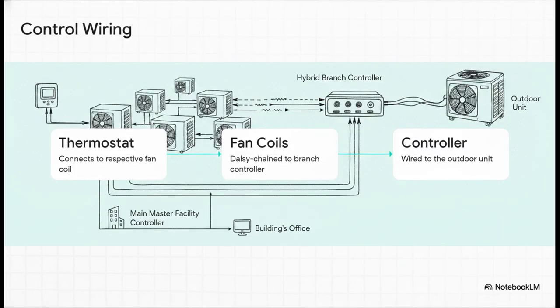So how do you manage all this hardware? Well, the control wiring is elegantly daisy-chained, kind of like a standard VRF system. Each thermostat wires directly to its respective fan coil. Those fan coils are then daisy-chained together all the way back to the hybrid branch controller. And finally, the branch controller is wired straight to the outdoor unit. This unbroken chain lets the outdoor unit discover and communicate with every single connected component seamlessly. And hey, if you need centralized oversight, it's super easy to wire a master facility controller from the building's main office straight back to the outdoor unit.